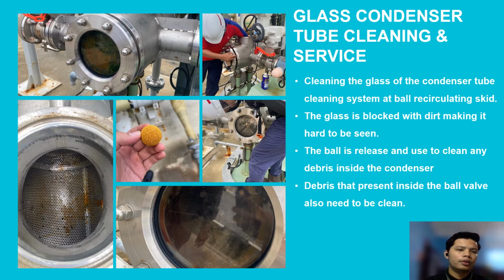So the next activity is cleaning and servicing the glass condenser tube from any dirt at the ball recirculating skid. The function of the system is to clean the condenser tube by releasing spongy yellow balls to enter the condenser and bring any dirt away from the tube. The dirt will form at the glass condenser and needs to be cleaned. The activity is shown in the picture.